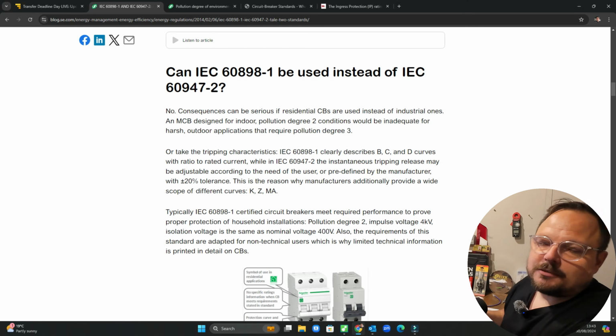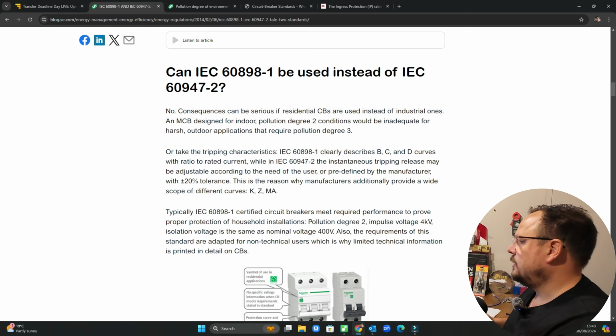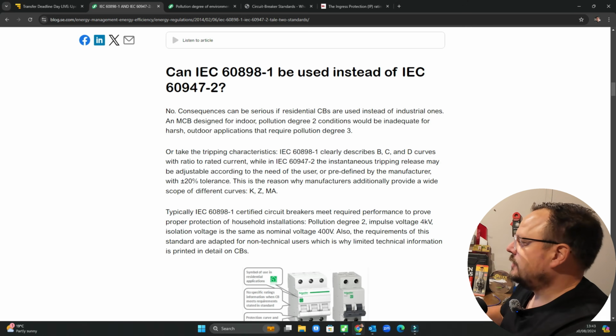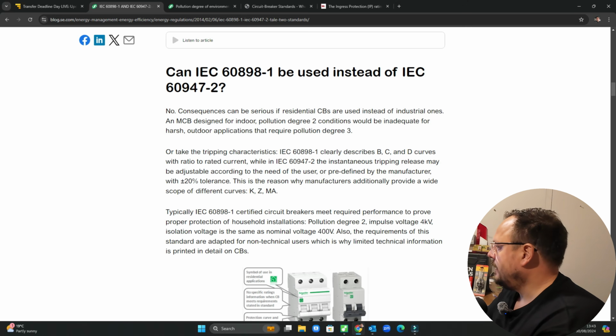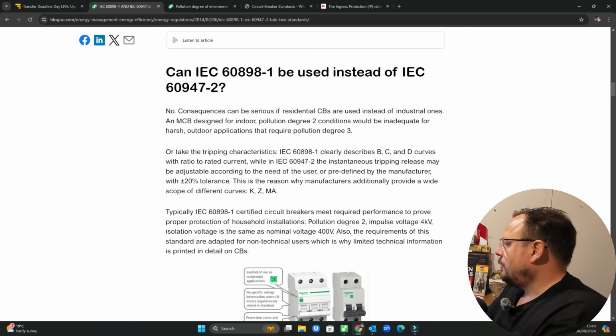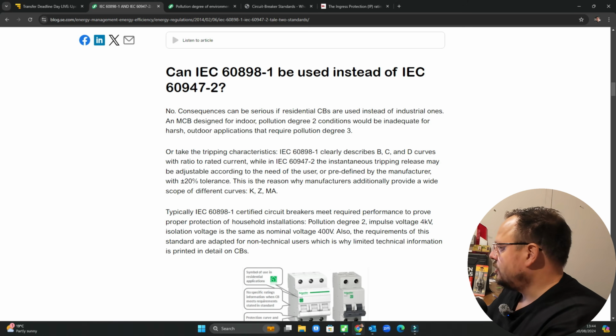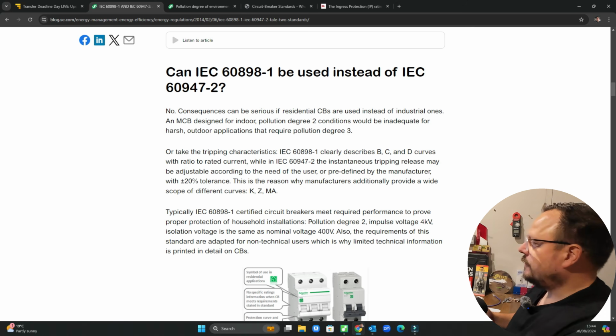So this is some of the other aspects that I mentioned where we were looking at the devices themselves. When you get those different tripping characteristics and the tolerances within, you can see it's talking about plus and minus 20%. At the bottom here it says typically IEC 60898-1 certified circuit breakers meet the required performance to prove proper protection of household installations, pollution degree 2, impulse voltage of 4 kilovolts, and isolation voltage is the same as nominal voltage, 400 volts.